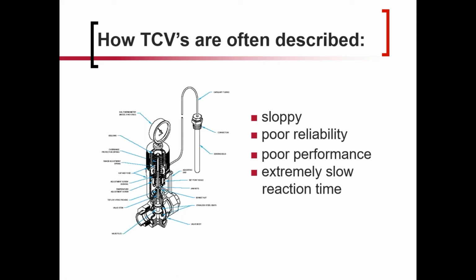But the reason that there is some lag, for lack of a better term, is you have this thermal fill. And for instance, let's say it's a heating application. Well, that fill needs to vaporize within the system and vaporize enough to actually close the valve. And that takes time.